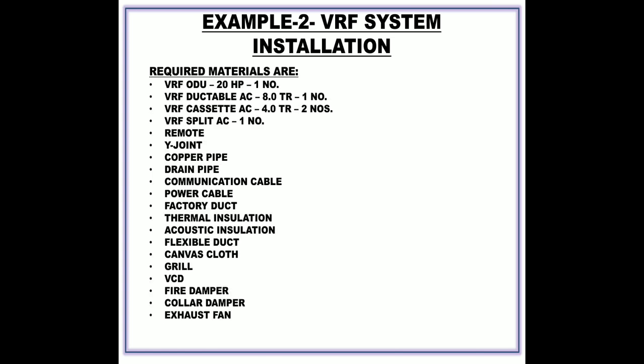Second example is installation of a 20 HP VRF system. Here we have 20 HP VRF ODU, ductable unit, cassette unit and high wall split unit. For their connection, we have copper pipe, drain pipe, cable, and air distribution items such as ducting, grill, VCD, fire damper and exhaust fan. These can be classified into high side and low side as shown.